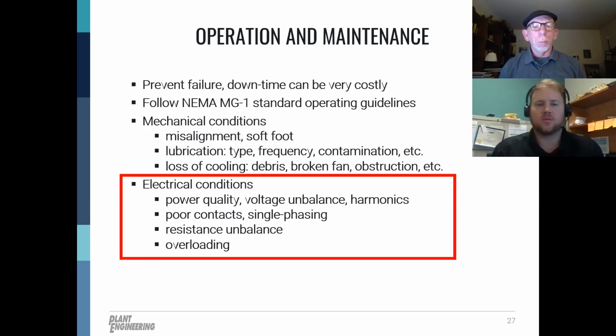And then, like I said, you can use your ampere meter to verify current draw if you got access to the terminals, the motor leads. Once you have the current readings, you can take those current readings and compare to motor nameplate full load amperage. And then additionally, another point of reference, if you have the motor de-energized, you can verify your winding resistance of the motor. A lot of your basic multimeters will check winding resistance. Now, it may not be the most accurate, but it's going to give you an idea. You should see really balanced phase-to-phase resistances.